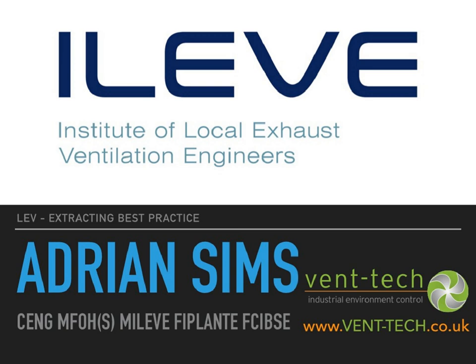So you need to take all things into consideration when designing stack discharge velocities. The British Occupational Hygiene Society course P602 looks at design of stacks - that's what I would recommend for this protocol. There's very little other guidance out there on stack discharge velocities. There is some information in the Environment Agency document, but you can still get hold of that from the British Library. There's also an American document from the American Conference of Government Industrial Hygienists, or ACGIH, that has some information on stack discharge velocities, but you'd have to buy that - it's from the States and costs about $200.